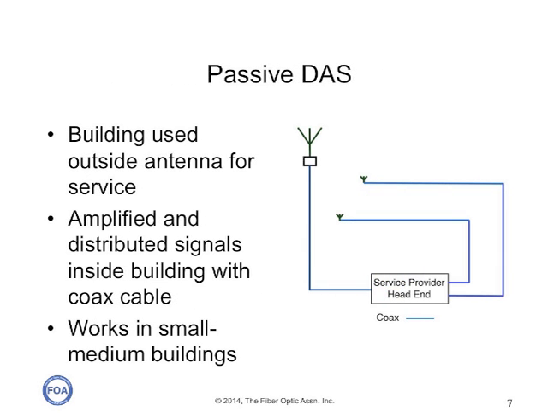There are two different types of DAS: passive and active. Passive DAS systems are simply repeaters for signals to and from an outside antenna. The electronics amplify the signals and connect to remote antennas over large, typically 12 to 25 millimeter, coaxial cables. Besides the obvious noise problems with all analog systems, the coax cable runs are limited to about 100 meters (330 feet).